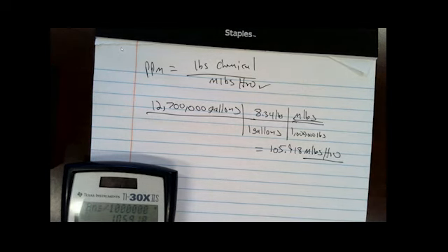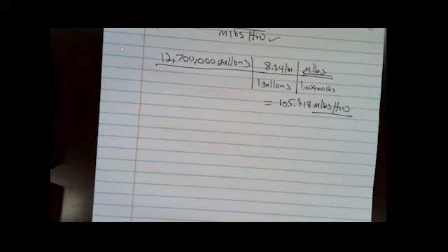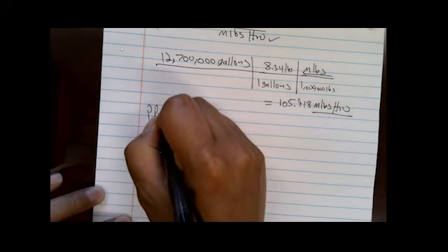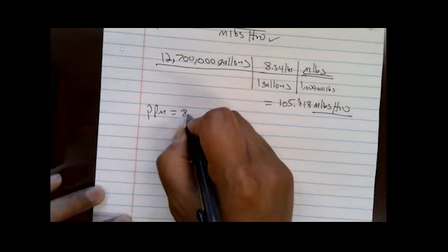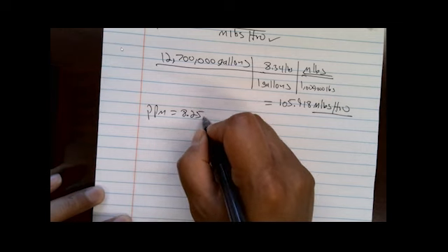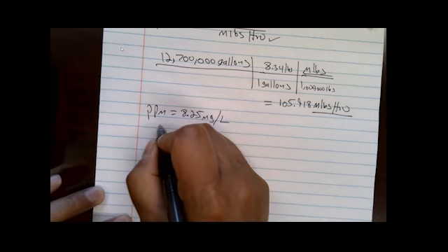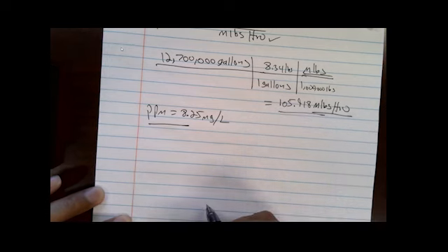And from the problem statement, it's asking us how many pounds per day of liquid alum are used if the flow rate is 12.7 million. So we're being asked for pounds per day of liquid alum, right? So this is where the percent of dry alum, the percent equivalent, 48%, comes into play, right? Let's also write down the part per million that we already have, 8.25, and that's milligrams per liter. So we have this, we have the million pounds of water.